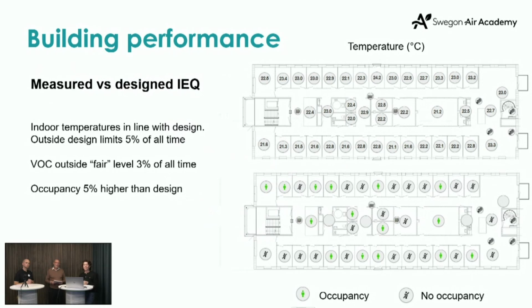And the VOC level, or the air quality, is fair or better 97% of the time in the building. This that I show here is print screens from the room management system, where we can see one floor of the building. On top we see the temperatures, and on the bottom we see the occupancy or non-occupancy. So I would definitely say we are meeting the demands when it comes to indoor environmental quality. And this is from a very HVAC perspective that we're looking at this.